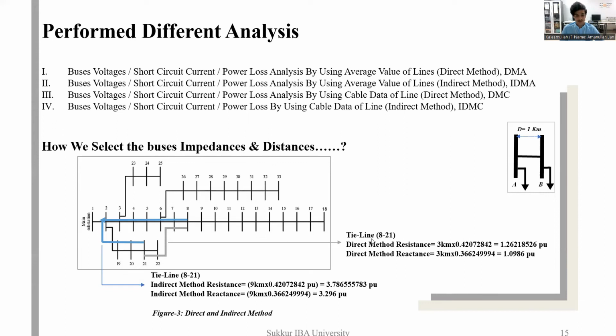So here is the calculation for the tie line resistance and reactance. By using the indirect method, we have connected a tie line from 8 to 21, whose distance can be measured as 9 kilometers, and whose calculation is given as shown. So in this way, we select the bus impedances and distance.